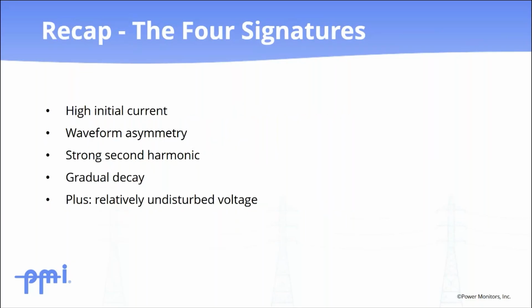So to recap, transformer energization is a routine, normal operation, but it leaves a very distinctive fingerprint in PQ data. If you remember the four signatures of high initial current, waveform asymmetry, a strong second harmonic, and gradual decay, and pair them with a relatively undisturbed voltage waveform, you can confidently identify these events and avoid misclassifying them as faults. As PQ monitoring keeps spreading across the grid, recognizing these kinds of patterns is going to remain a core skill for anyone doing PQ analysis.